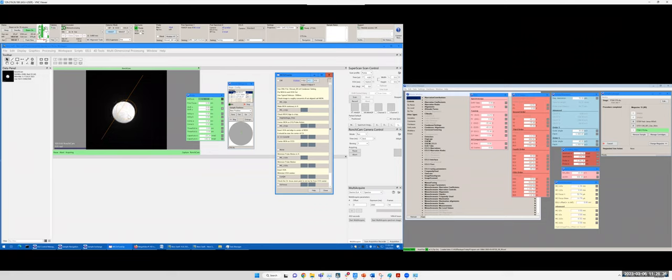Do you see the effect? I'm pointing at the center of the expansion and shrinking of the gold particle images. I want to align this position to the center of the VOA. So I want to change VOA so that those wobbling centers are the center of VOA. Okay, do you follow me? Do you see the wobbling center is the center of this aperture now? I can move it far off, right? You can see the effect. You can see that the center of the aperture is here, right? So I can bring it back so that it's aligned. Okay, now it's aligned.